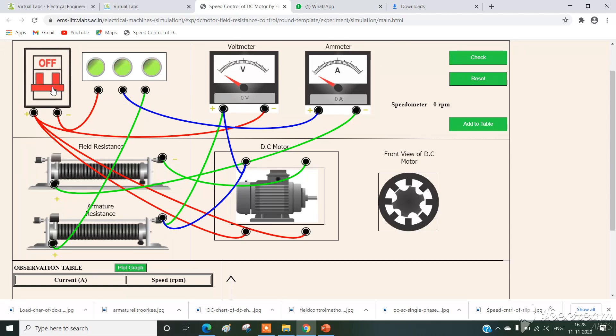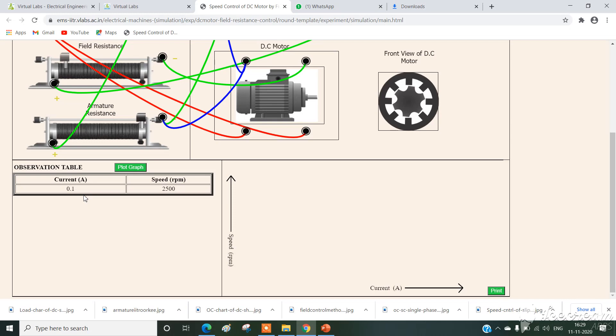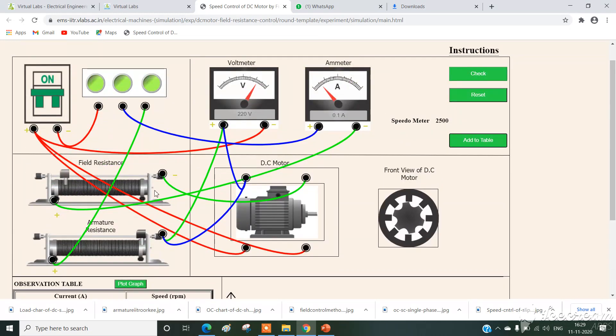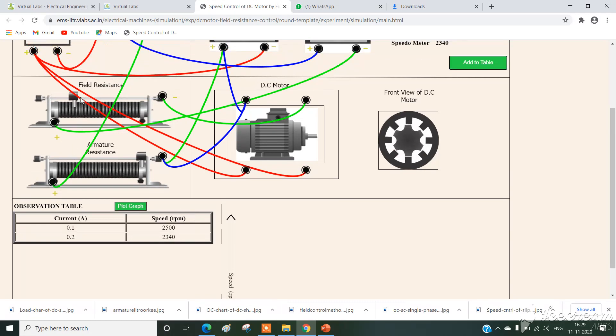Switch on the power supply by clicking on the switch — supply is now on. In the field control method, first apply the rated voltage to the machine. For the first reading, click on add to table: field current is 0.1 and speed is 2500. Next, vary the field current to 0.2 — field current increases, so correspondingly, due to the inverse relation, speed reduces. We need to take a minimum of 6 readings.